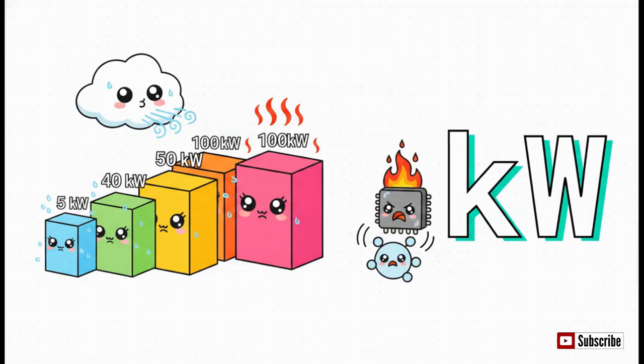To really grasp the scale of the problem we're facing today, we have to look at one massive number: 100 plus kilowatts. Traditionally, a standard server rack pulled maybe 5 kilowatts of power. Today, with the boom in deep learning and these gigantic GPUs, extreme AI racks are jumping from 5 to 40 to 50, and even over 100 kilowatts per single rack.